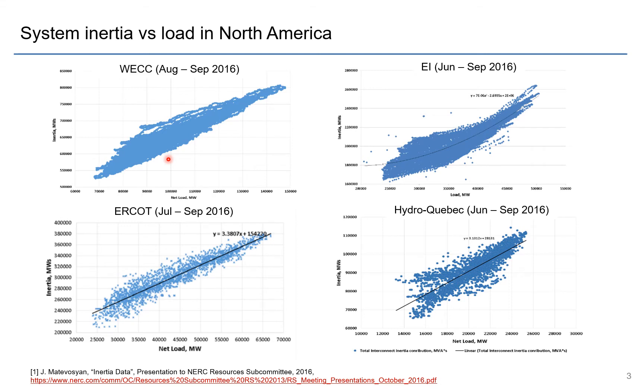You can see very clearly a strong positive correlation between load and inertia — as load goes up, inertia goes up, which makes sense because more generators are online at higher load. More interestingly, some of these correlations are non-linear and flatten out at low loads. This suggests there is a minimum amount of synchronous generation connected to the system regardless of load — probably due to large thermal facilities like coal and nuclear that can't or won't turn off because it becomes expensive. This sets natural inertia floors for some systems, though not all of them — some remain quite linear.